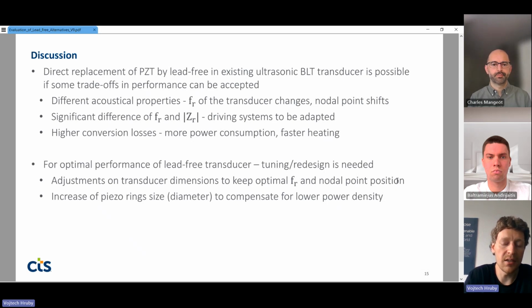A significant difference of resonance frequency and also impedance magnitude at resonance requires some adjustments in driving systems. Also, due to higher conversion losses, more power consumption of the transducer and faster heating can be expected when it comes to lead-free alternatives.